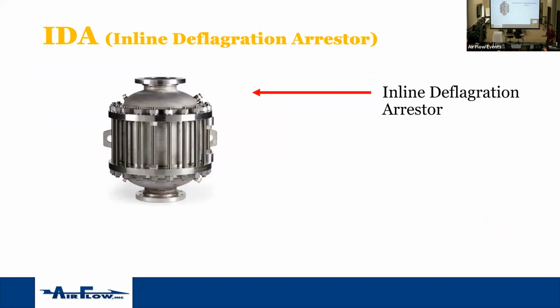The option of not doing inline deflagration internal to the filters is to add a secondary device. This happens to be a small one, but what this does is it will actually take that flame ball, send it through a series of fine mesh filters and screening, and it actually knocks that flame ball down and allows the pressure to go through without the flame. It's pretty costly.